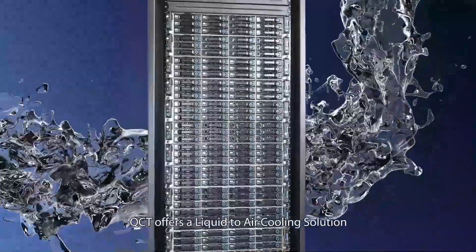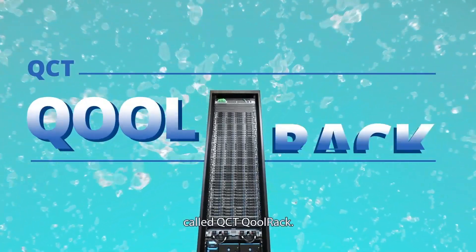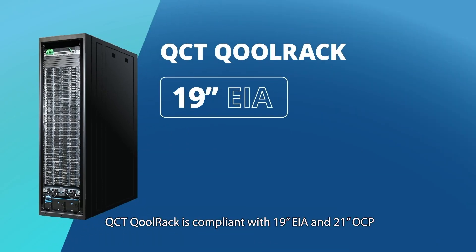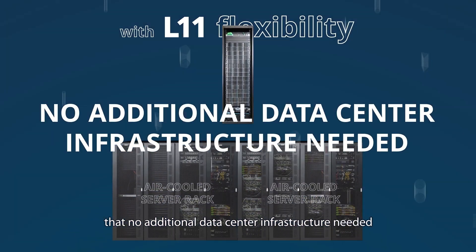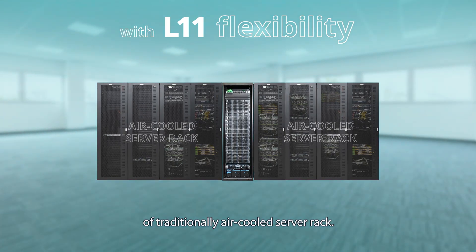For that reason, QCT offers a liquid-to-air cooling solution called QCT QoolRack. QCT QoolRack is compliant with 19-inch EIA and 21 OCP open standards with L11 flexibility — no additional data center infrastructure needed — and can be placed alongside any brand of traditionally air-cooled server rack.